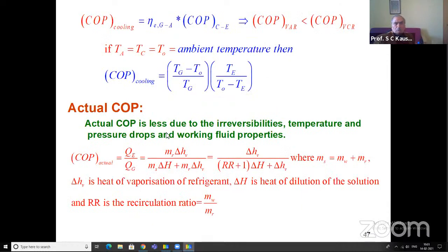So the overall COP of the vapor absorption cooling system is based on the heat engine efficiency of the generator absorber assembly, and the vapor compression part is between the condenser and the evaporator. If we use a common sink temperature for the condenser and absorber, then we have the overall ideal efficiency of the vapor absorption system. As compared to a vapor compression cooling system, this heat engine efficiency is involved, which is much less than 1. So the overall COP of the vapor absorption system is lower than the COP of the vapor compression system. But that can be understood.